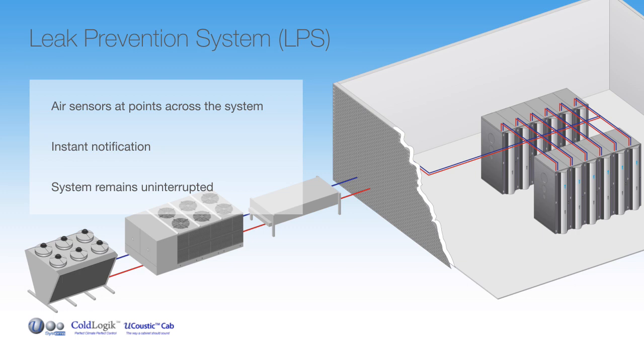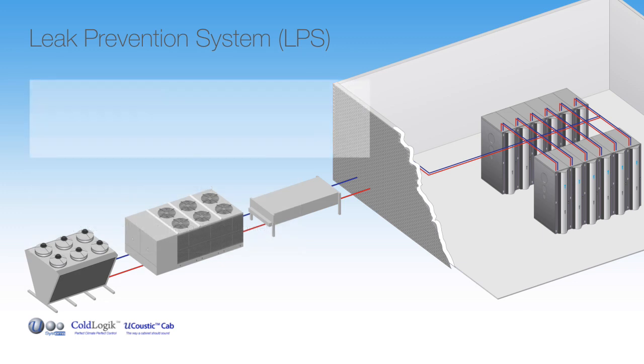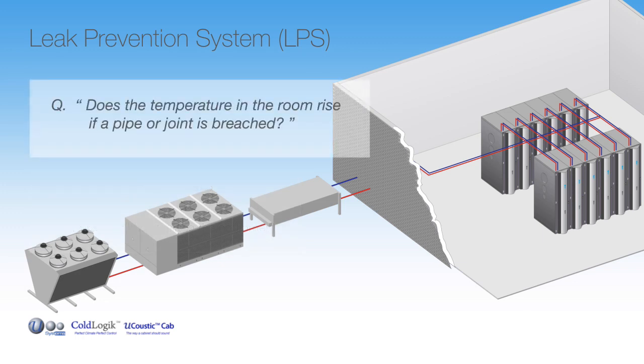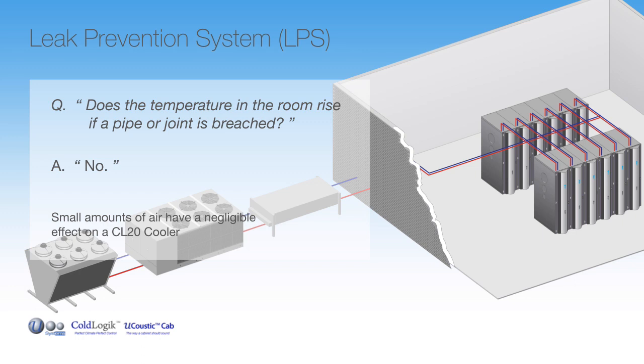The advantage with this technological ecosystem is that the data center manager can locate the fault, plan the maintenance, and carry out the remedial work without risk to the equipment or general environment. A commonly asked question is whether the temperature in the room rises if a pipe or joint is breached. The simple answer is no. Only a relatively small amount of air would pass into the circuit, which on an individual CL20 cooler would have a negligible effect, and certainly could not destabilize a data center.